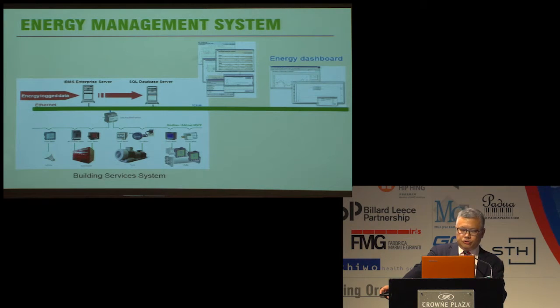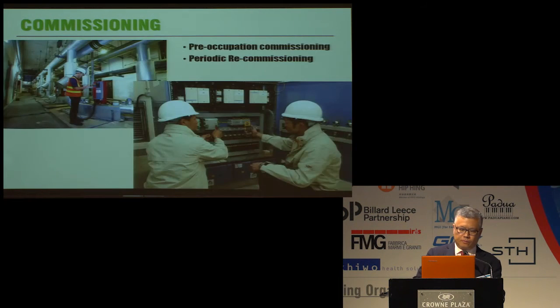A building management system with direct digital control will provide comprehensive control and monitoring of the building services systems, but adequate provision of metering is required. Energy dashboards provide instantaneous energy use information to facilitate the operator to optimize energy efficiency. Commissioning not only ensures the building services systems perform properly according to the design, but also can help improve the building energy efficiency through fine-tuning of the set points and the control logics to suit the actual operational requirements during pre-occupancy and early post-occupancy periods. Just as your car requires to be tuned up periodically, hospitals are no different. Hospitals are dynamic buildings that undergo constant changes during their lifetime to suit the operational requirements. So recommissioning should be carried out periodically so that systems can be recalibrated to maintain functional performance and improve energy efficiency.